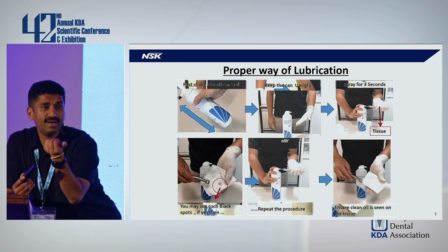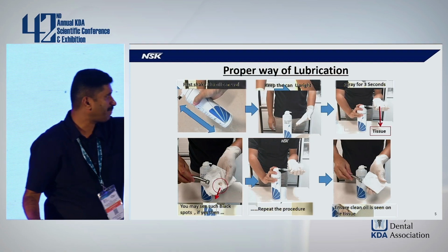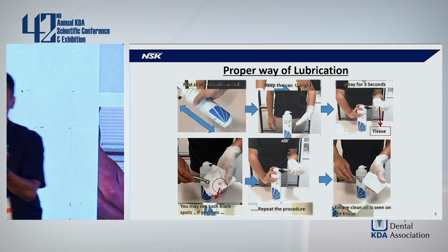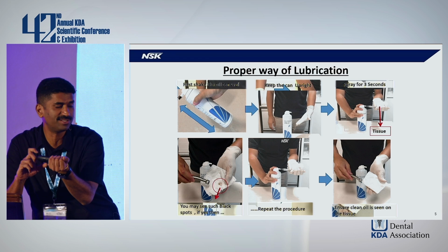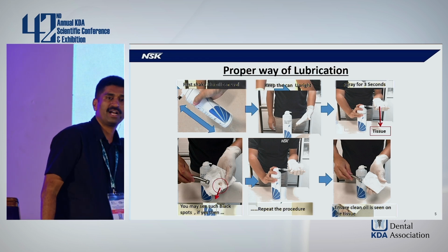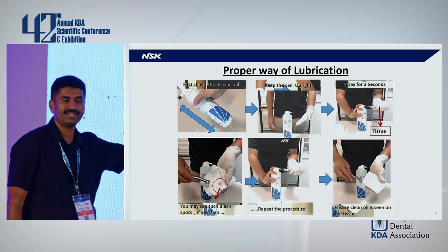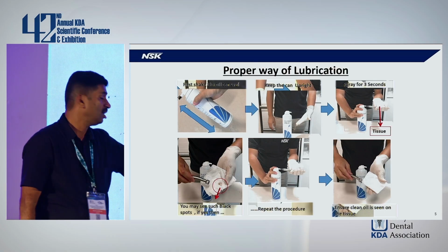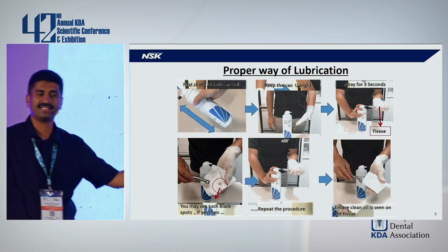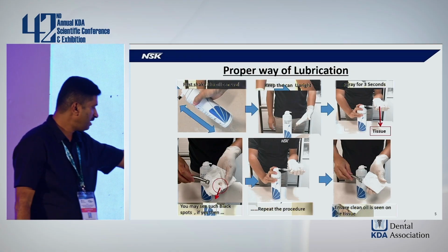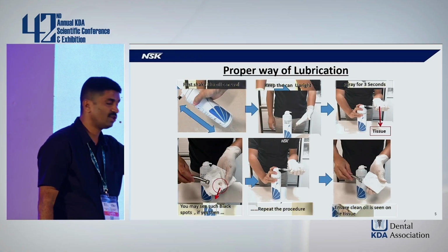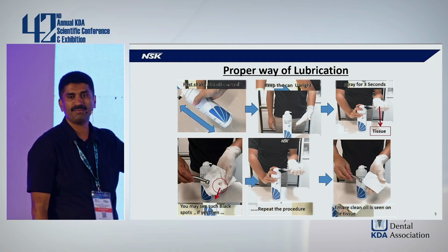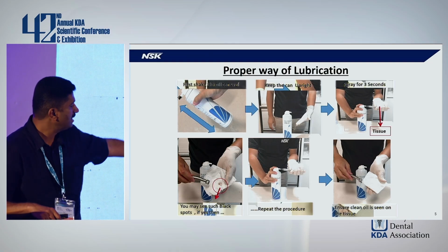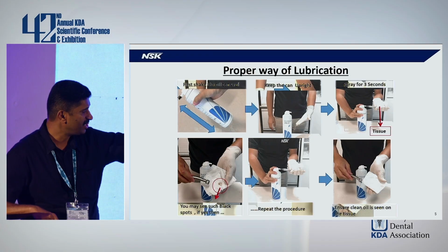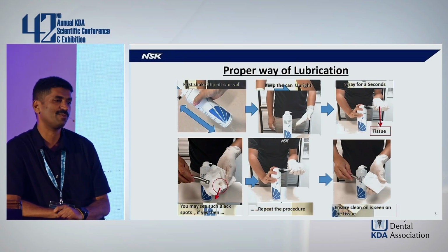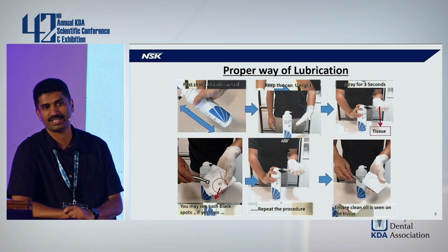During this time, cover the head of the handpiece with a tissue paper. Very important. You cover the head of the handpiece with a tissue paper, spray for 3 seconds, and see what's coming out from your handpiece. Unless you cover this with a tissue paper, you will not be able to know whether it's pure oil coming out or whether it's debris or blood or whatever. So only when you cover it with the tissue paper, you exactly know what is coming out. If you see some blackish or brownish or reddish particles, repeat the procedure until you get clean oil coming onto the tissue paper. Very, very important.